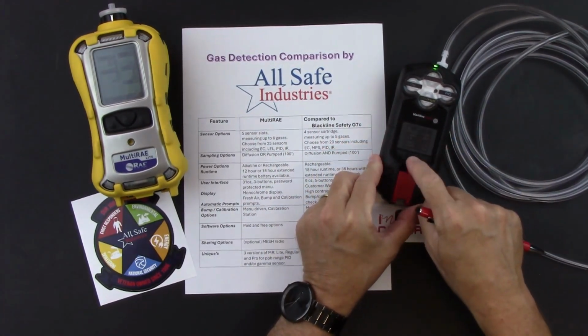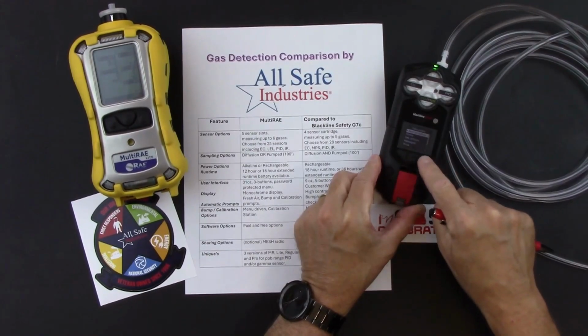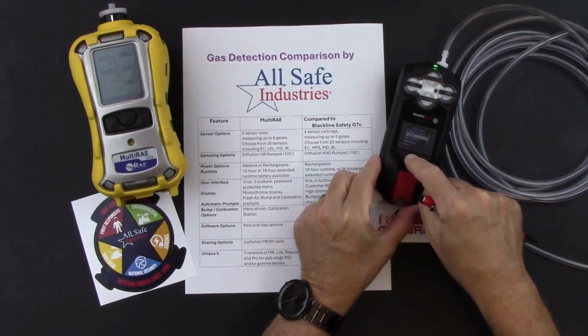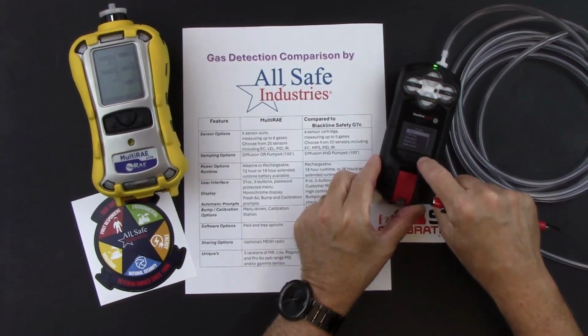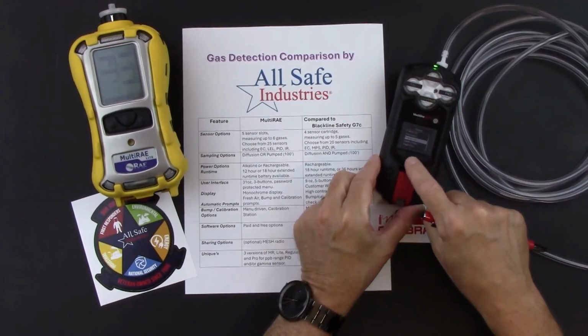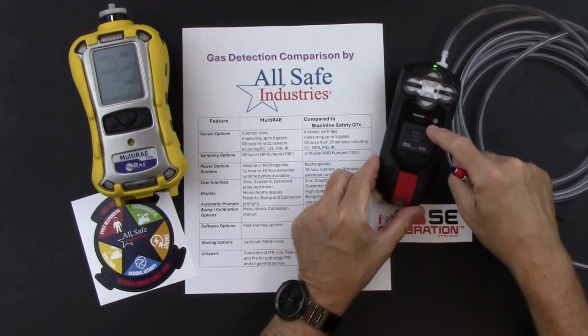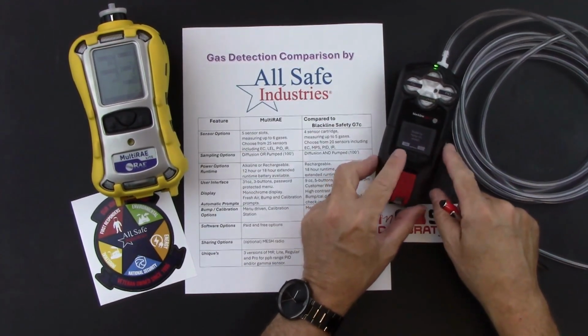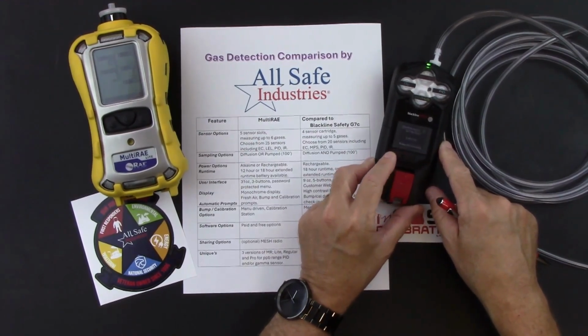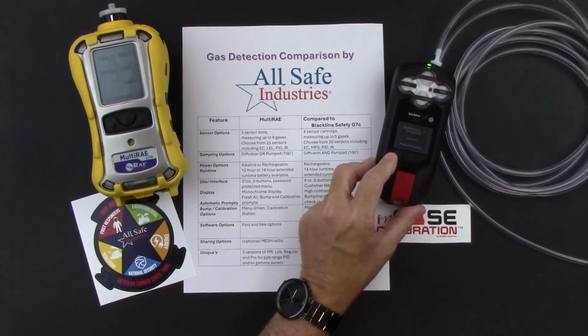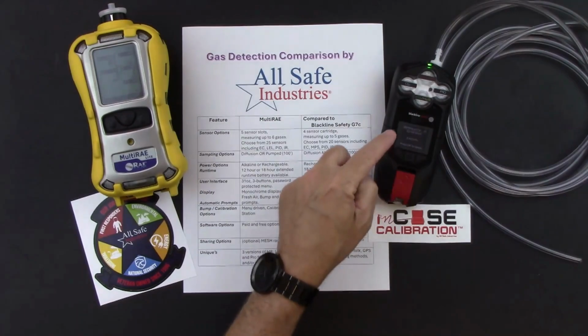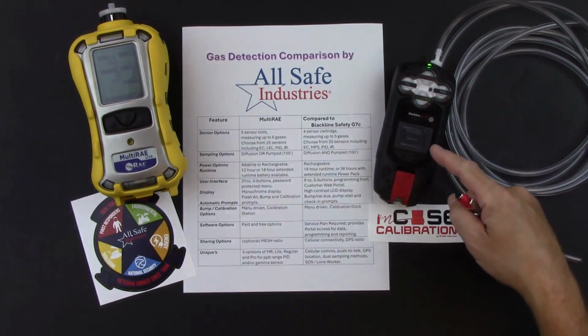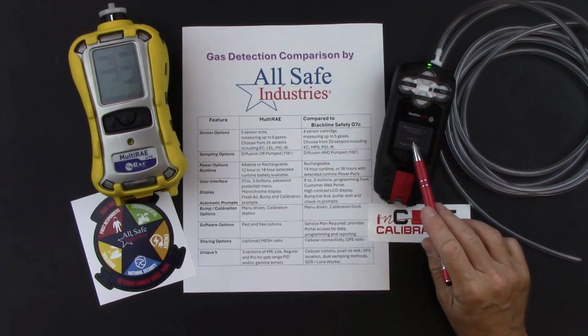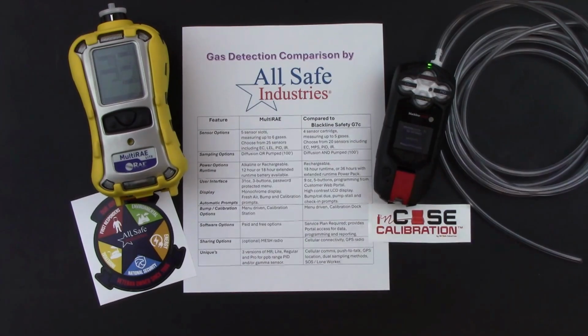My screen timed out, so I've got to go back into it. So I'm going to drop down to modes, hit OK. I want to drop down to pump run, hit OK. And then it says switch to pump run mode, and I want to select yes. So right now it's starting up the pump. You'll see that it says do not block while it's doing this initial boot up, and you'll see that the flow rate will start to increase here.